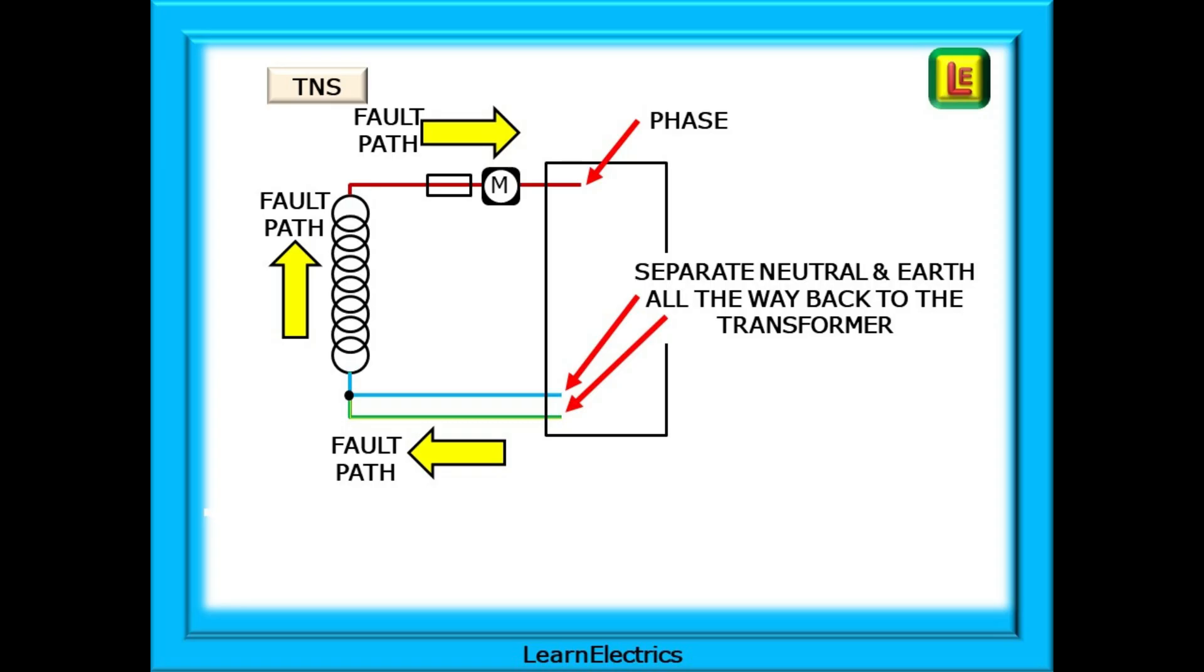This is important, because, if the fault current did not flow along the phase wire, and back through the fuses, then the fuse would not blow, or the breaker would not trip. No flow through the fuse, and the fuse won't blow. When the fuse or breaker operates, the fault current will stop, and the installation will be in a failed safe condition, awaiting repair.